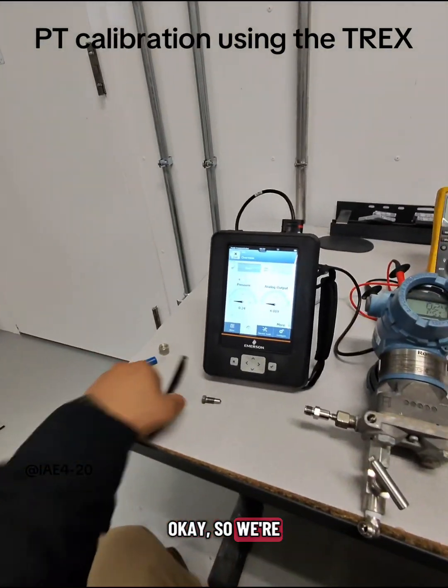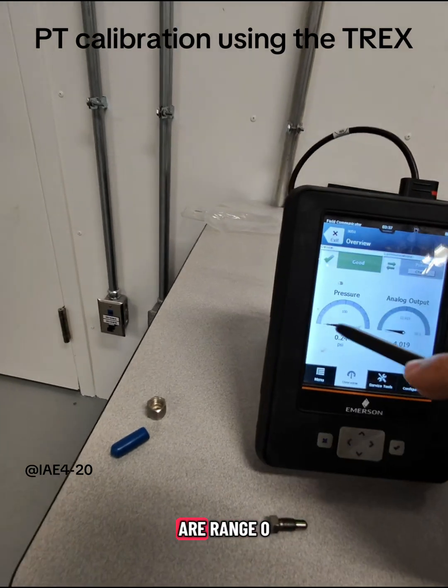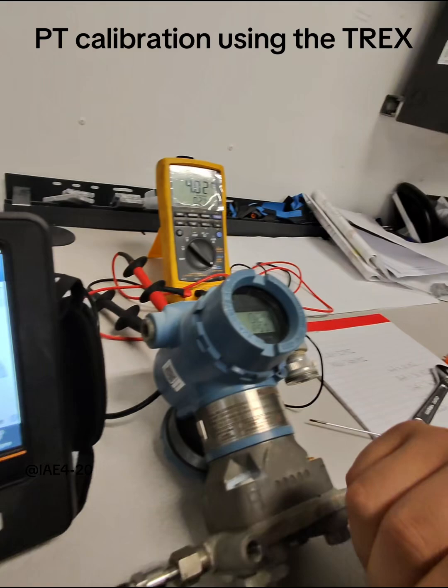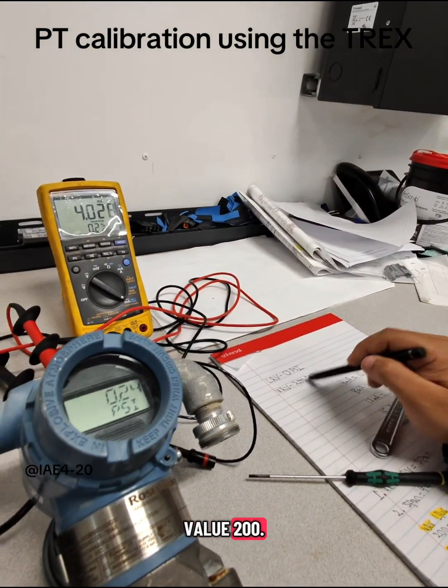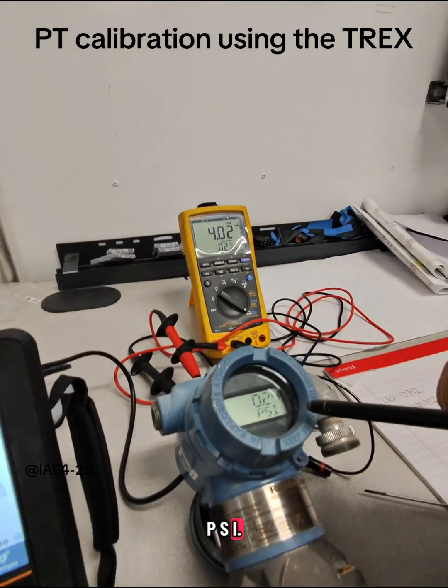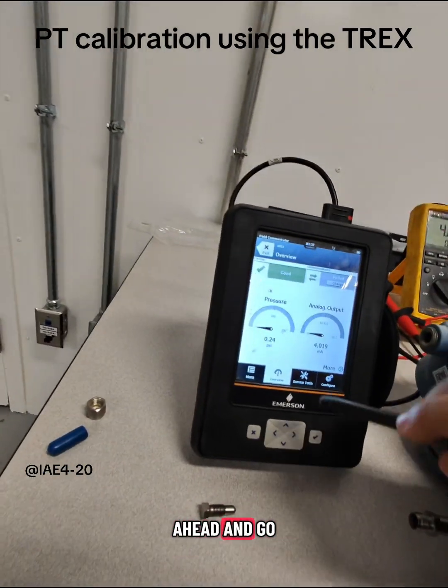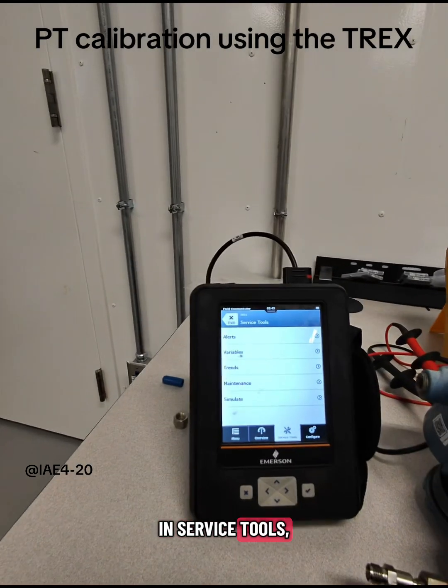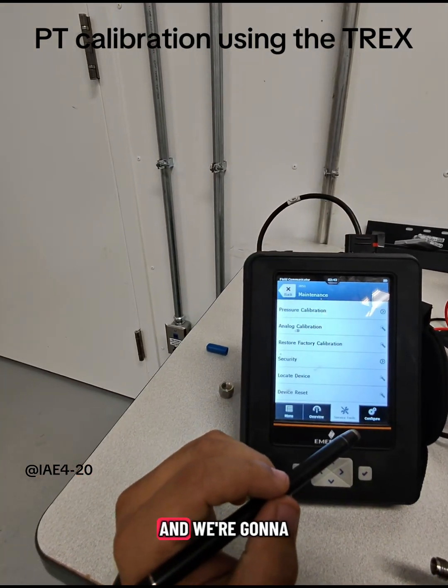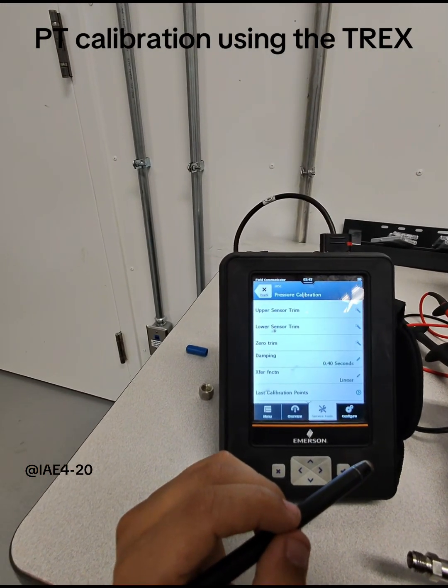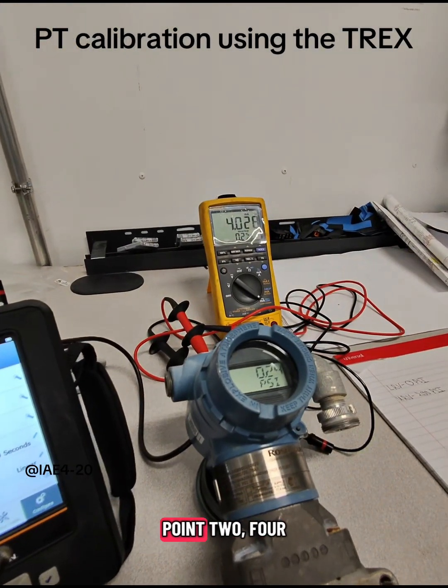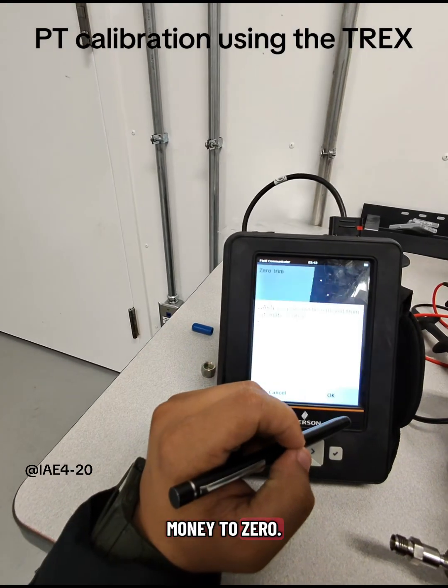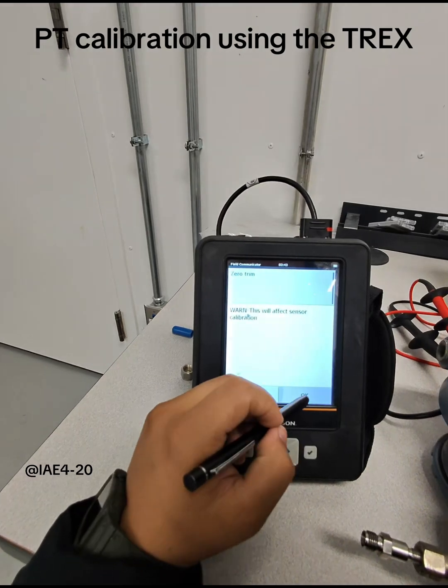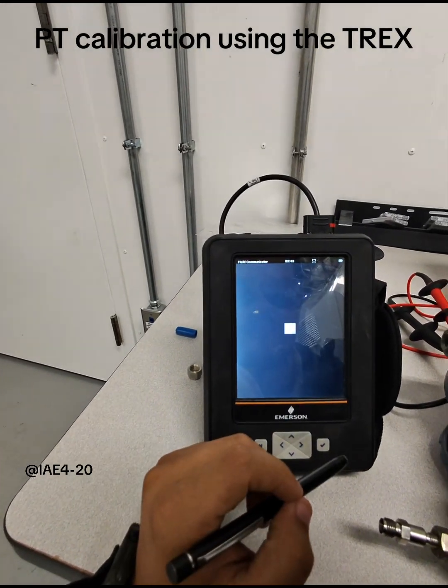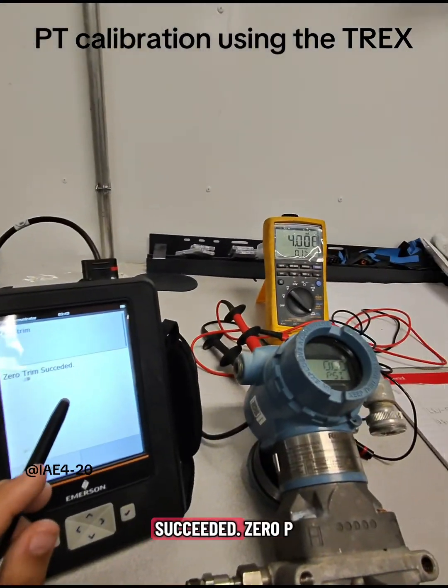Okay, so we're going to go ahead and look that we are range 0 to 200 psi, low range value 0, upper range value 200. We are reading 0.24 psi and 4.02 milliamps. So we'll go ahead and go to service tools. Okay guys, now that we're in service tools, we're going to go to maintenance, and we're going to do pressure calibration. I'm going to go ahead and do a zero trim. We have about 0.24 psi. I want to get that on the money to 0. Zero trim succeeded. 0 psi, 4 milliamps on the money.